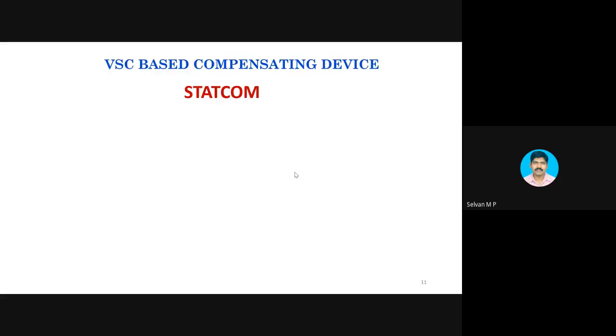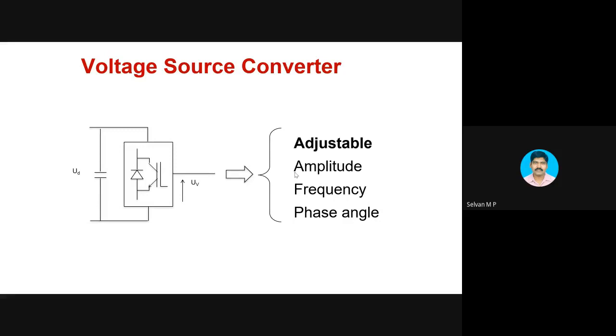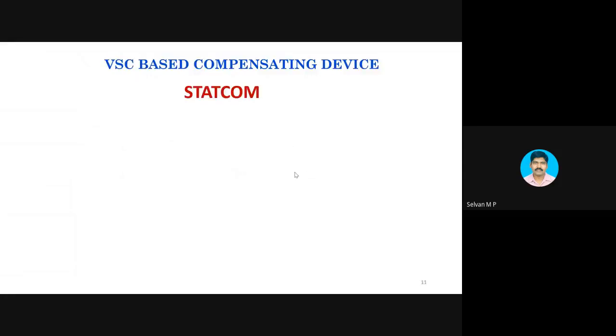So this voltage source inverter, if you use it for reactive power exchange alone, is called a STATCOM. STATCOM is otherwise called a second generation FACTS device. First generation FACTS devices are made only of thyristor based systems. Second generation FACTS devices are voltage source inverter based systems.